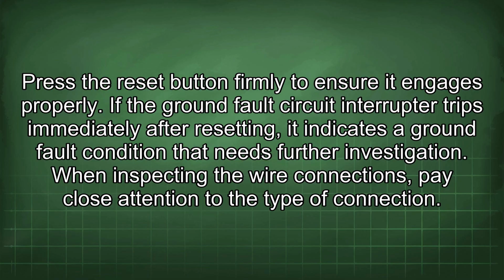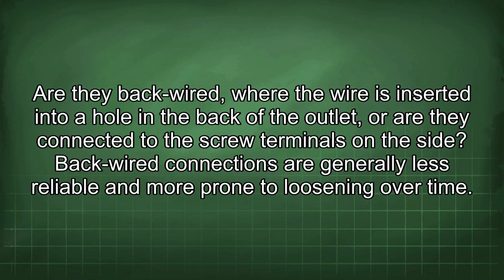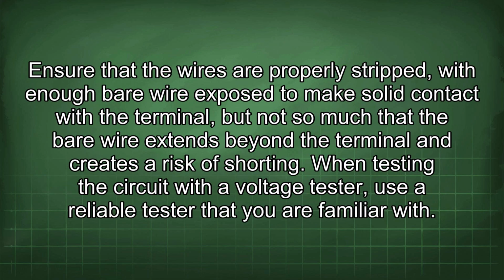When inspecting the wire connections, pay close attention to the type of connection. Are they back-wired, where the wire is inserted into a hole in the back of the outlet, or are they connected to the screw terminals on the side? Back-wired connections are generally less reliable and more prone to loosening over time. Ensure that the wires are properly stripped, with enough bare wire exposed to make solid contact with the terminal, but not so much that the bare wire extends beyond the terminal and creates a risk of shorting.